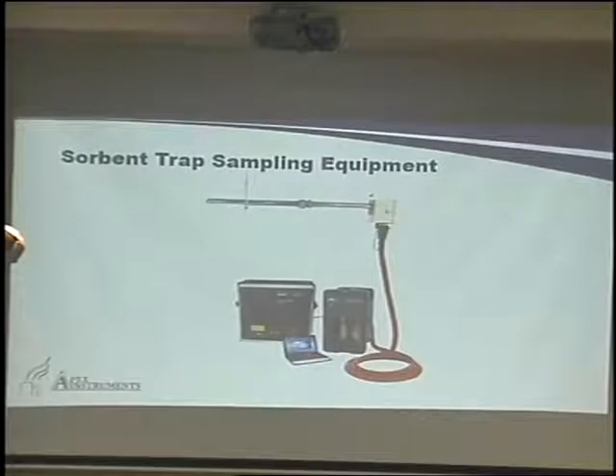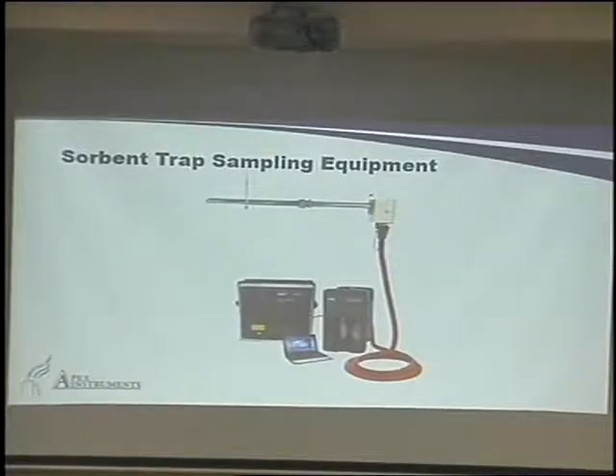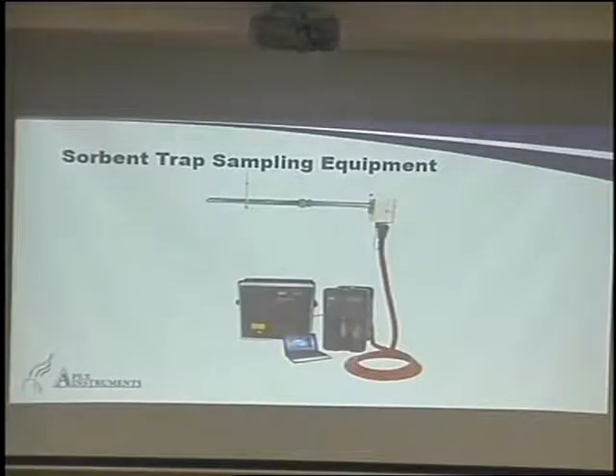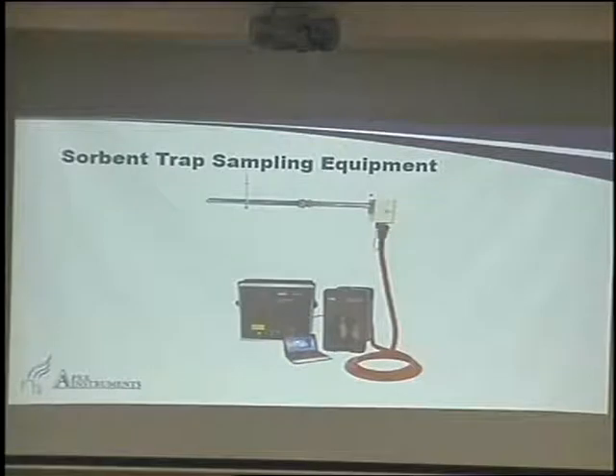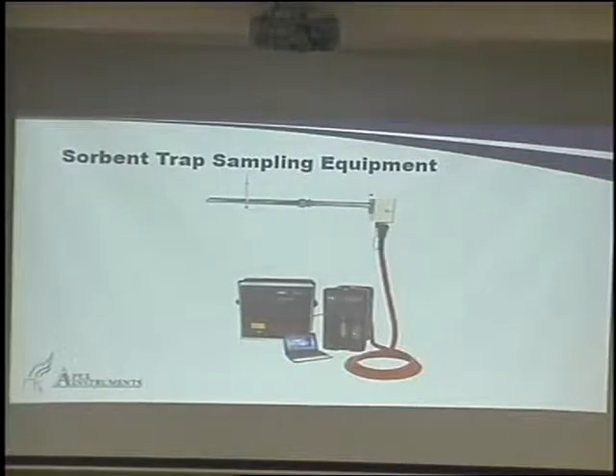Proportional sampling is the flow rate might be here, but we start sampling low down here. And if the flow rate increases, we also increase as well. But it does not match the flow. It's proportional to the flow, okay? So typically it's done around 1 or 2 liters a minute, right? Whereas the flow is going to be much faster than that. So say the flow is 20 liters a minute, and it goes up 10% to 22 liters a minute, and we're sampling at 1 liter a minute, we will go up to 1.1 liters a minute, okay? We're going to go up the same percentage as that flow changes. That's for PS12B, okay? The traps are the same.